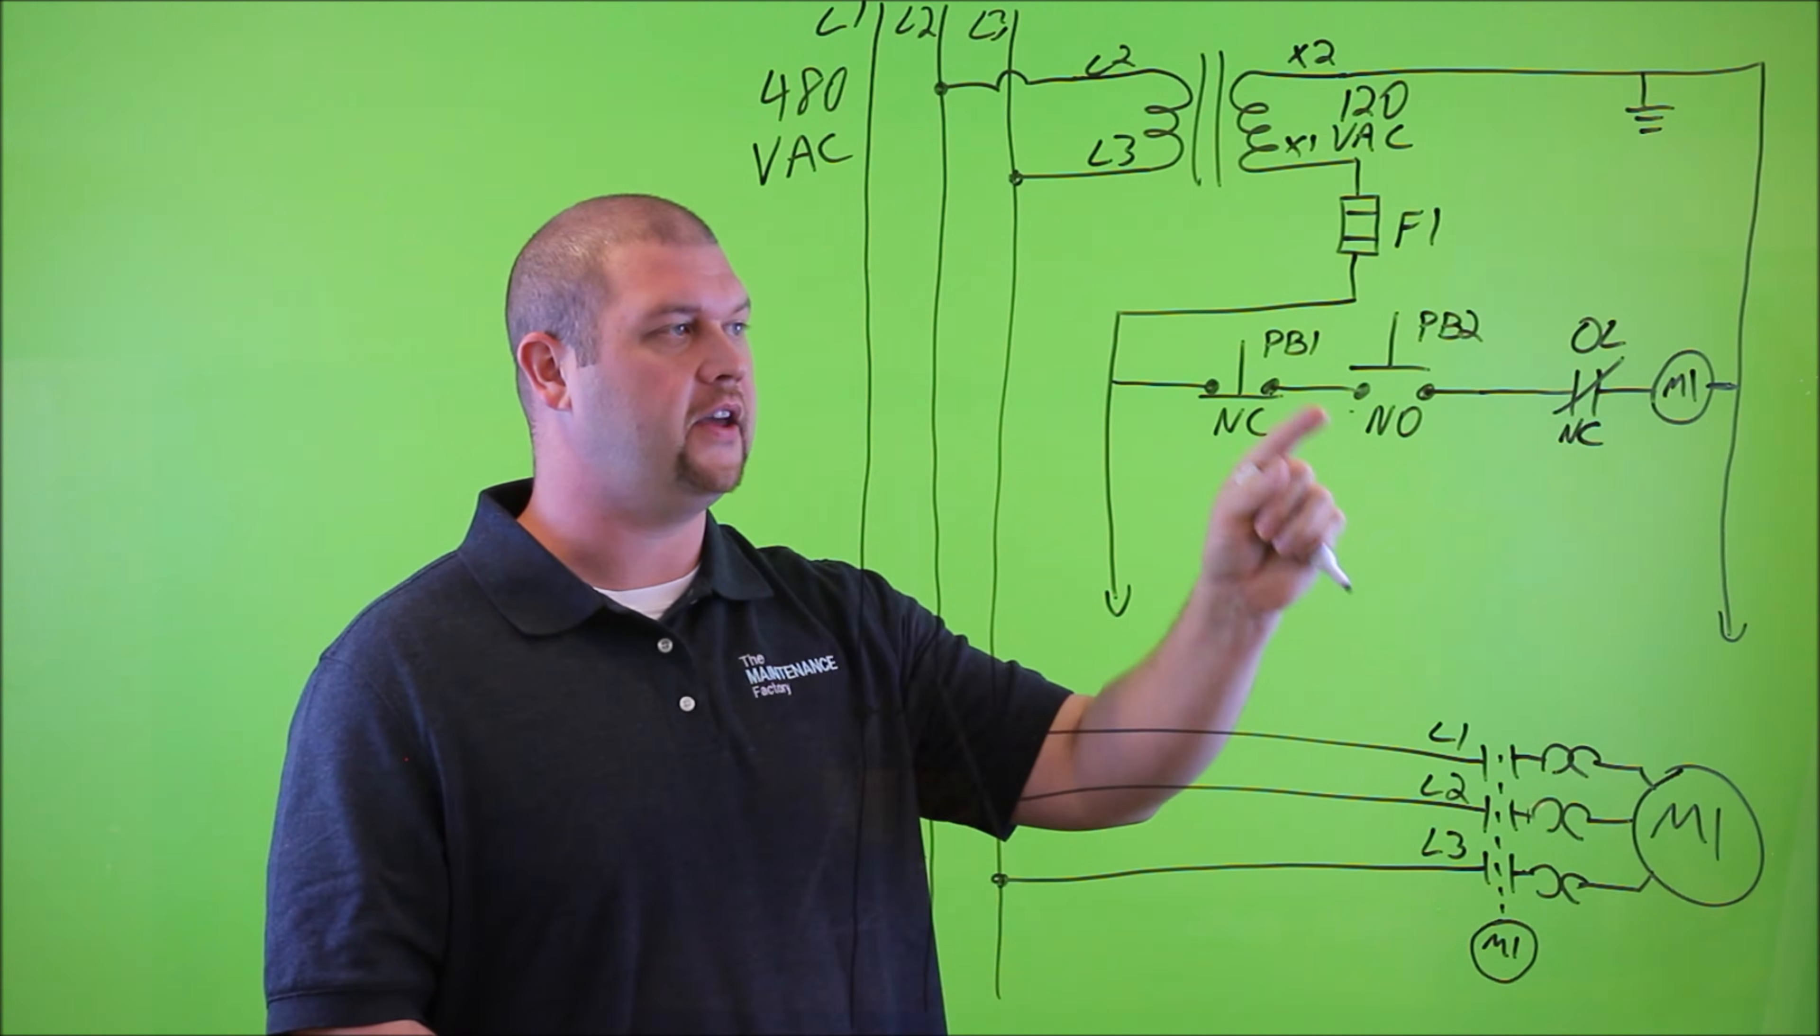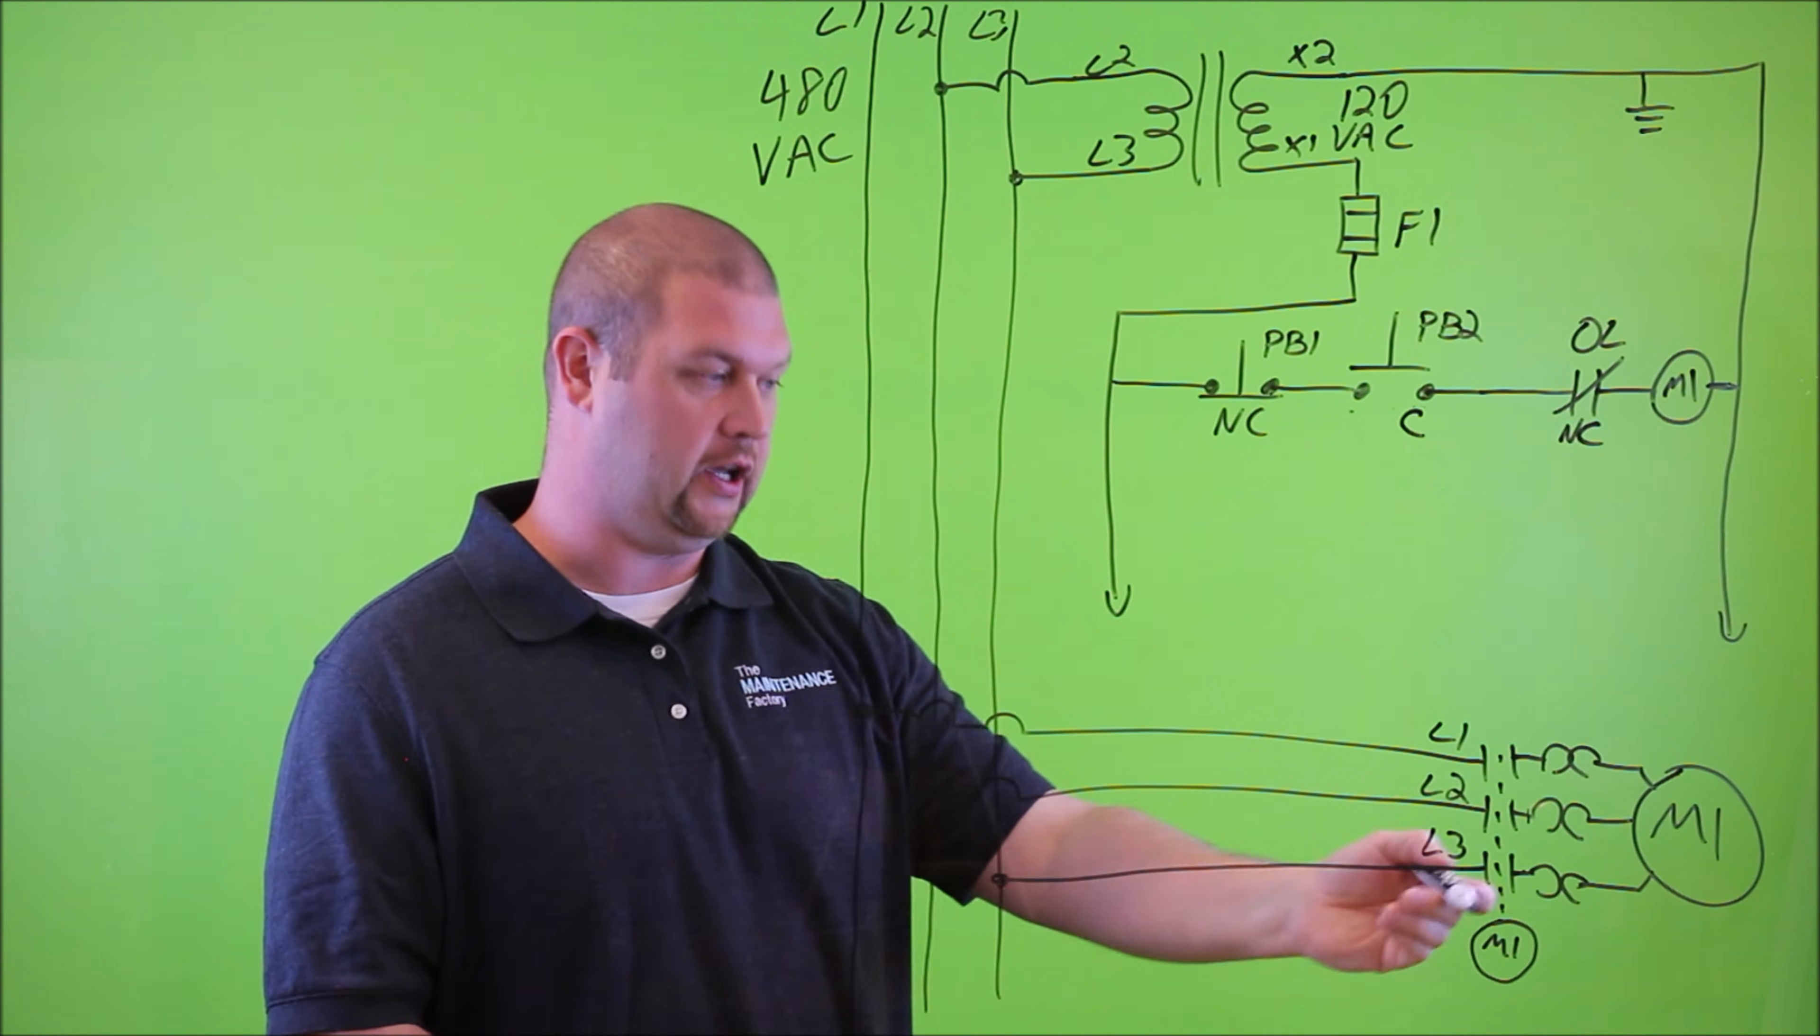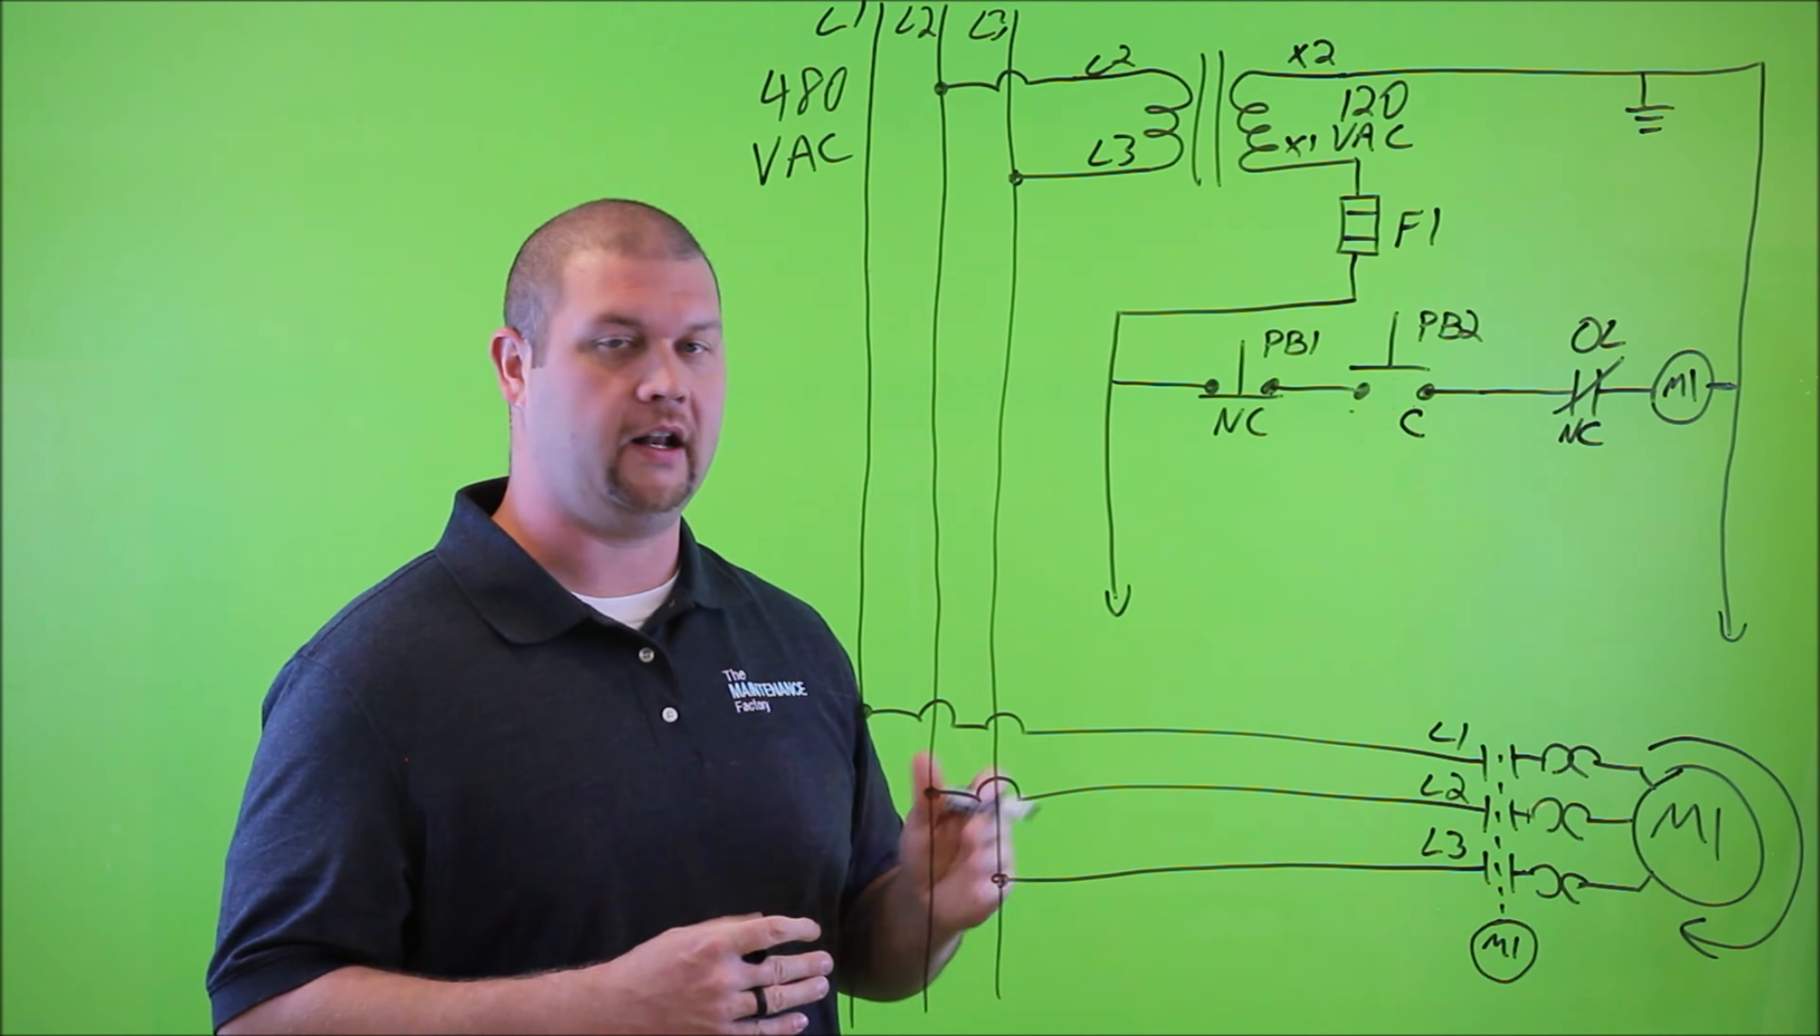So let's say that we would come along and then depress the start button, which is PB2. It's going to switch states from normally open to closed, and then that's going to provide a path for current to flow, and it's going to energize that coil, thus closing the contacts, providing power to the motor, and then the motor will then rotate. Now, that's fine and dandy if we want to sit here and continuously hold our finger on this button the entire time we expect the motor to perform work. But that's not an ideal condition.